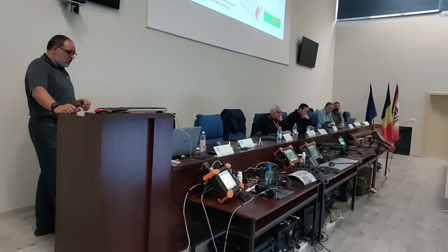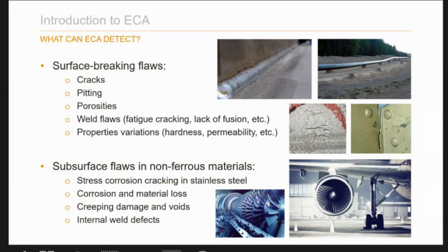So higher speed compared to a single element ECT, you have less dependency on the operator skills, for example. And you will end with a C-scan, a cartography, similar to what you have with the UT phased array, for example. What can ECA detect?